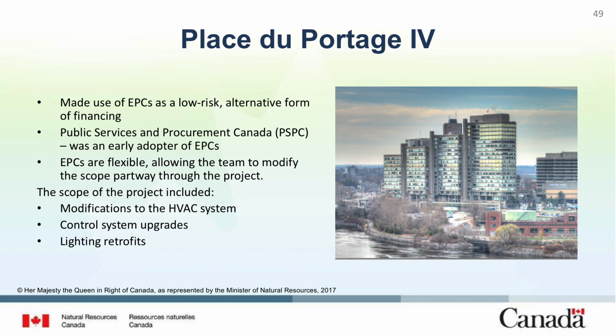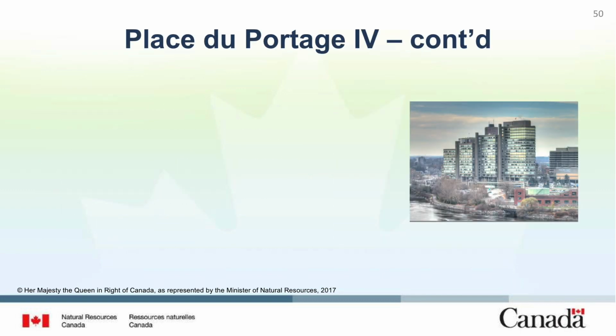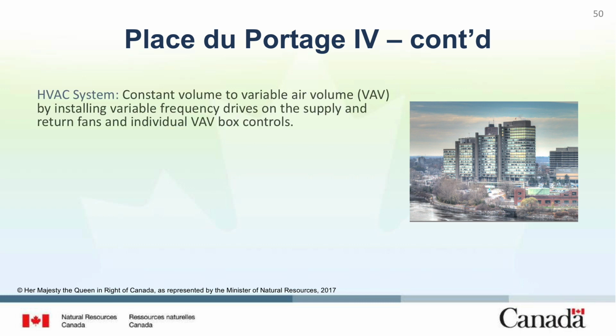The scope of the project initially included modifications to the HVAC system, control system upgrades, lighting retrofits, an upgrade and refurbishment of the cooling towers, and replacement of one of the facility's 3 chillers with a modern, efficient machine. Portage 4 was built with constant volume, dual-duct HVAC systems throughout the building.